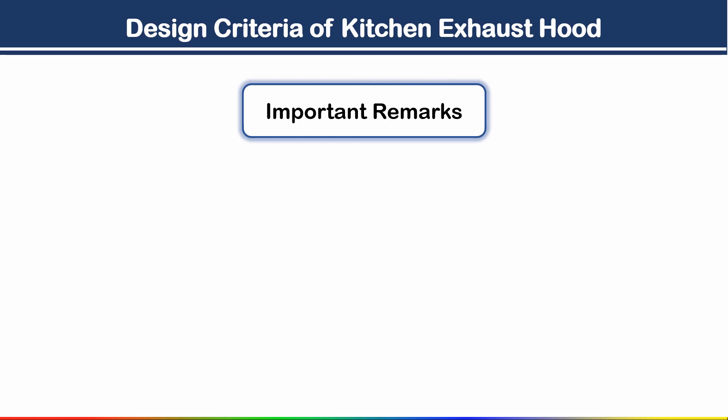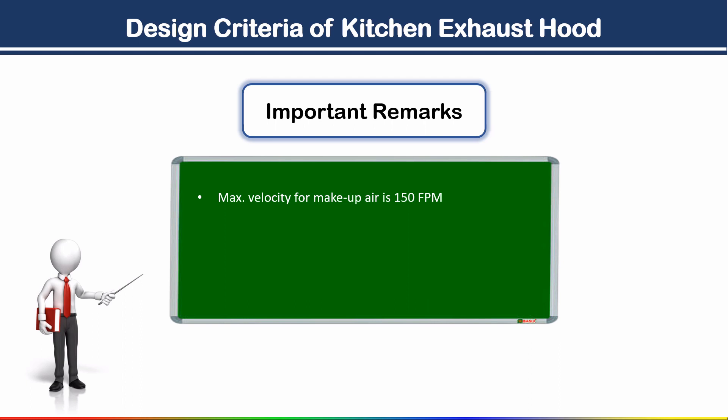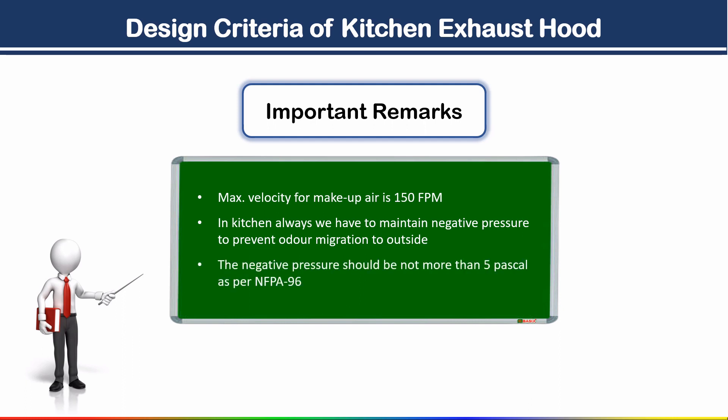Some important remarks: maximum velocity for makeup air is 150 fpm. In a kitchen, we always have to maintain negative pressure to prevent odor migration to the outside. The negative pressure should not be more than 5 Pascals as per NFPA 96.